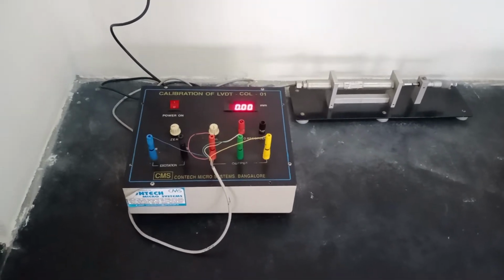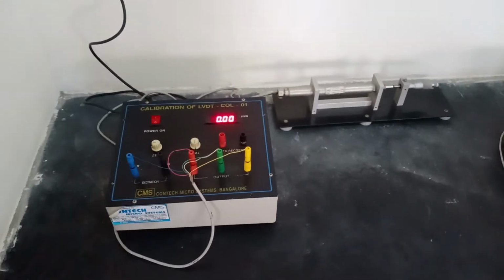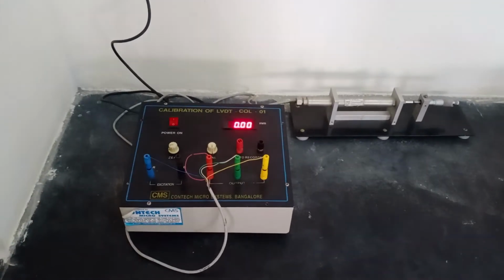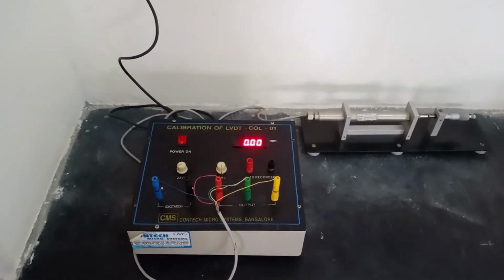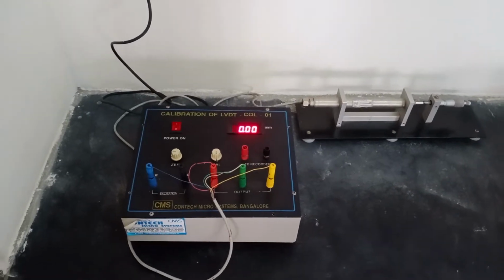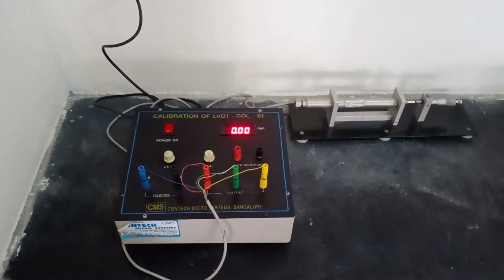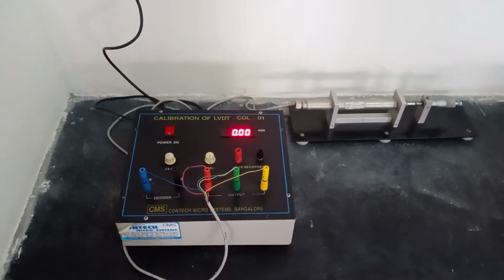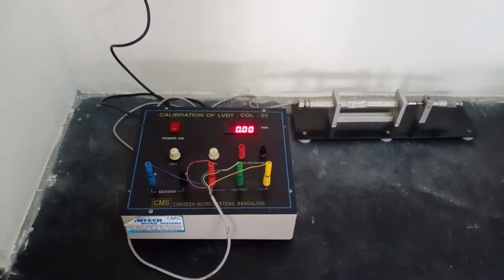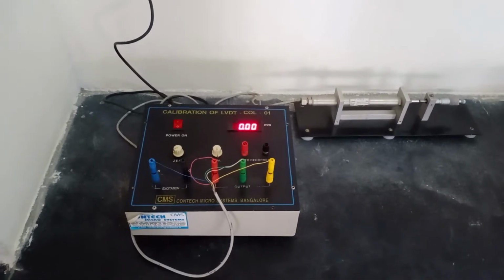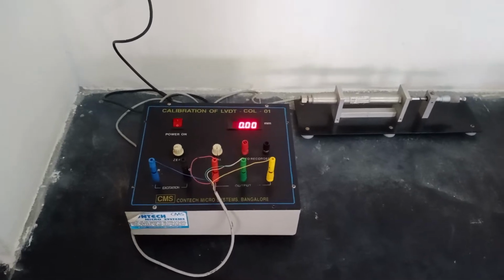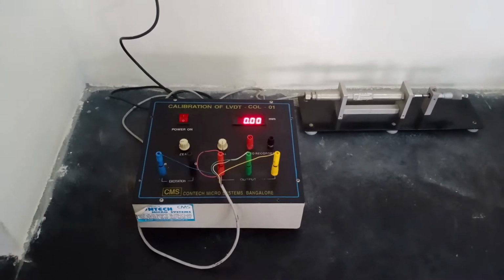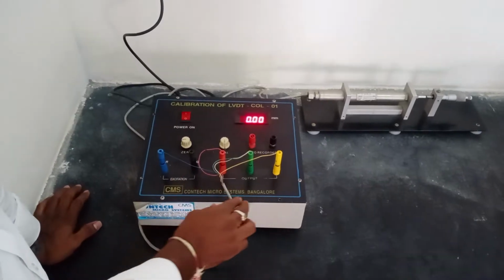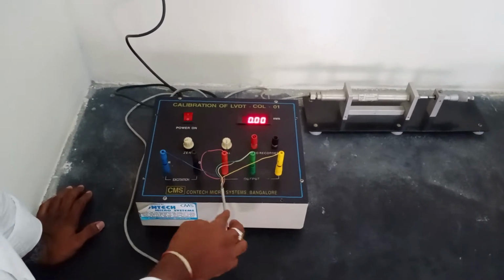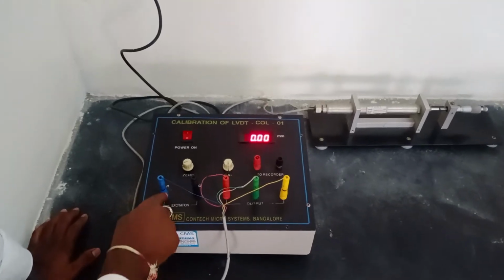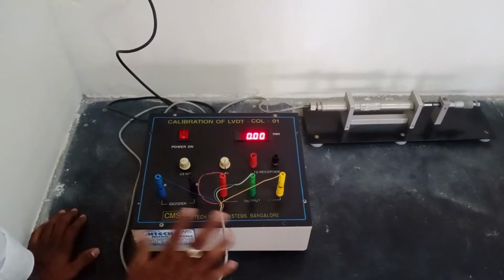respect to the LVDT. The major specification of the LVDT is plus or minus 10 mm. The distance measured on the micrometer is plus or minus 10 mm, and the micrometer range is 25 mm. The least count of the micrometer is 0.01 mm and the linearity is plus or minus 1%. All the cables or wires are connected to the color-coded ports, as shown on the device.